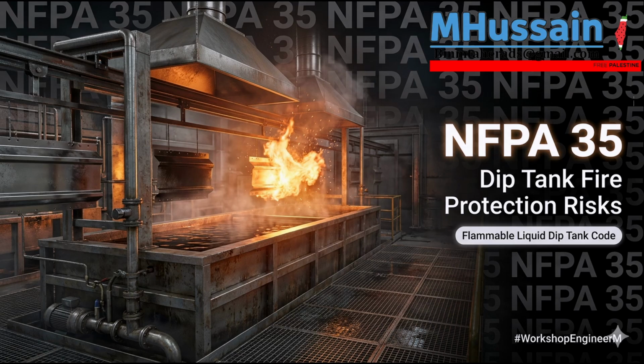Section 9.5.1 states unequivocally that all equipment, tanks, machinery, and piping where an ignitable mixture might be present must be bonded together and connected to a ground. And the standard doesn't just suggest it, it provides exact engineering resistance metrics that must be tested and verified. Yes, the numbers here are critical for the electrical contractors. For a metallic grounding path, like a copper wire connecting a steel tank to a grounding rod, the electrical resistance to ground cannot exceed 25 ohms. 25 ohms. For a non-conductive or semiconductive grounding path, it cannot exceed 1 million ohms, or 1 megohm.